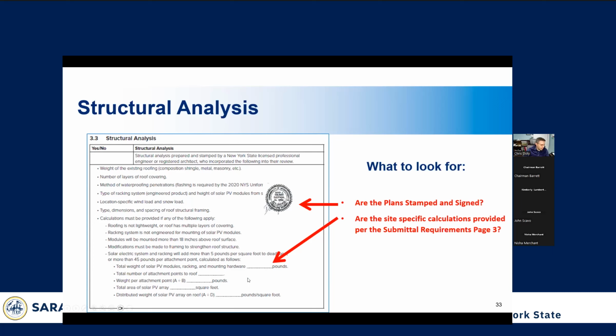You want to make sure, as I was talking about before, that the structure these panels are being installed on can hold the weight and will not have any structural issues from having a bunch of extra weight put on the roof. You want to make sure that all the values are accounted for and the calculations have been filled out and done properly. These are all site-specific calculations. Like I said before, it's not a one-size-fits-all thing at all. All buildings are different and every PV system is different. So it's very important to make sure that these are the actual values for this place. If you get 10 applications from a single contractor and they all have the same values, that's a pretty good indication that they're not really doing these evaluations correctly.